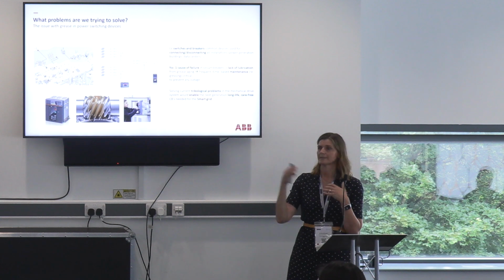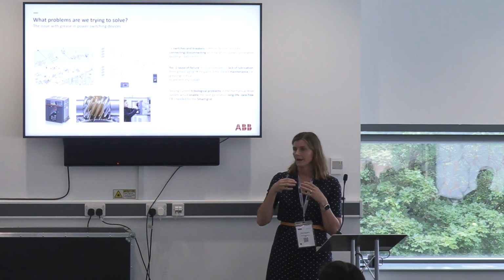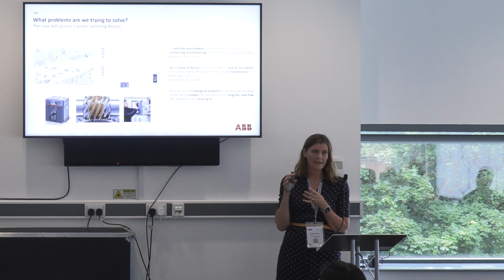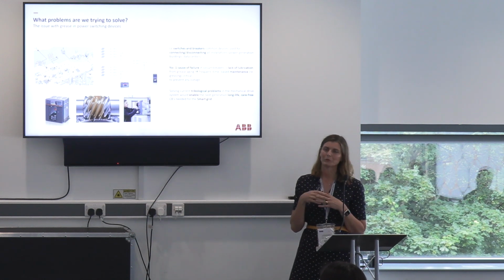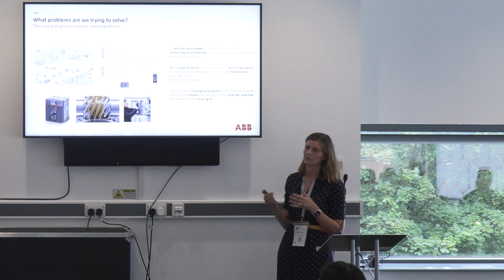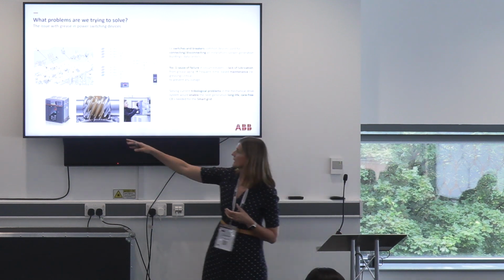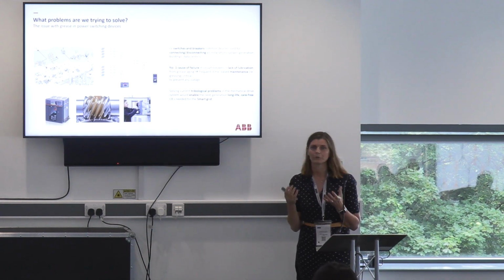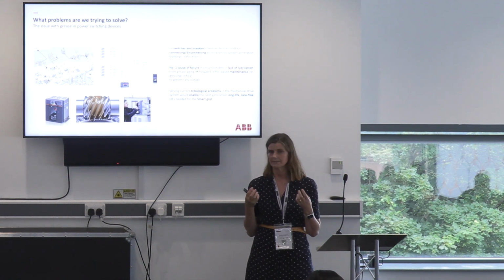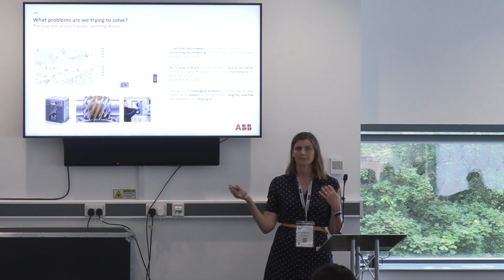The opening and closing operation of these devices has to happen very quickly, governed by a mechanical drive system that is grease lubricated. It cannot fail, because that could have catastrophic consequences for data centers and so on. But the mechanical drive system's grease has issues: it ages, becomes thick and viscous, and the operation can slow down or even stop functioning.